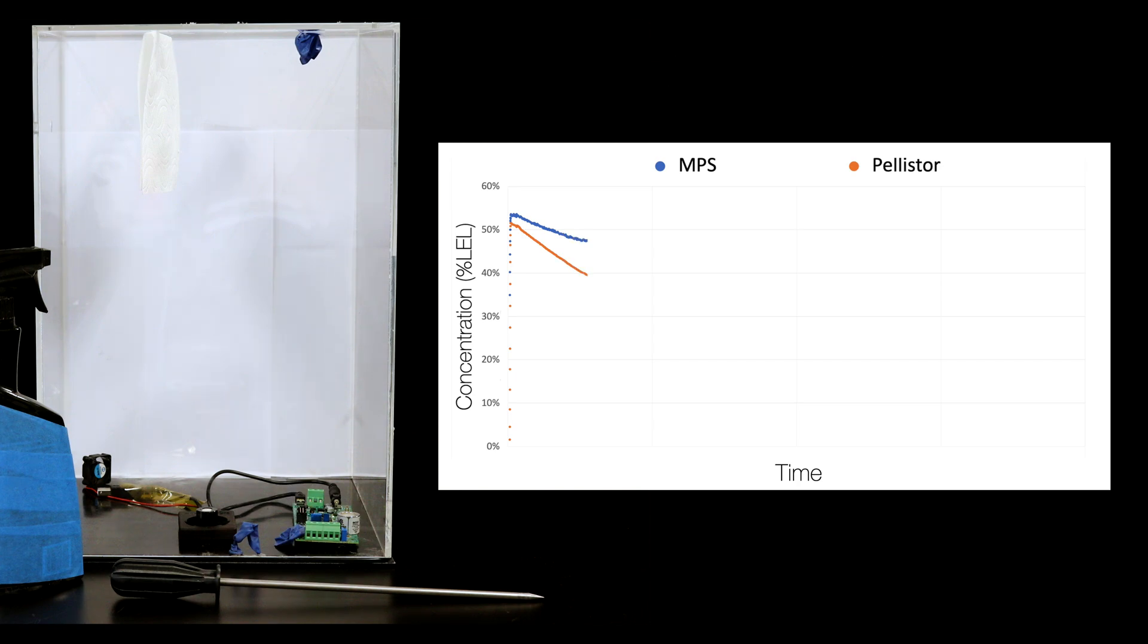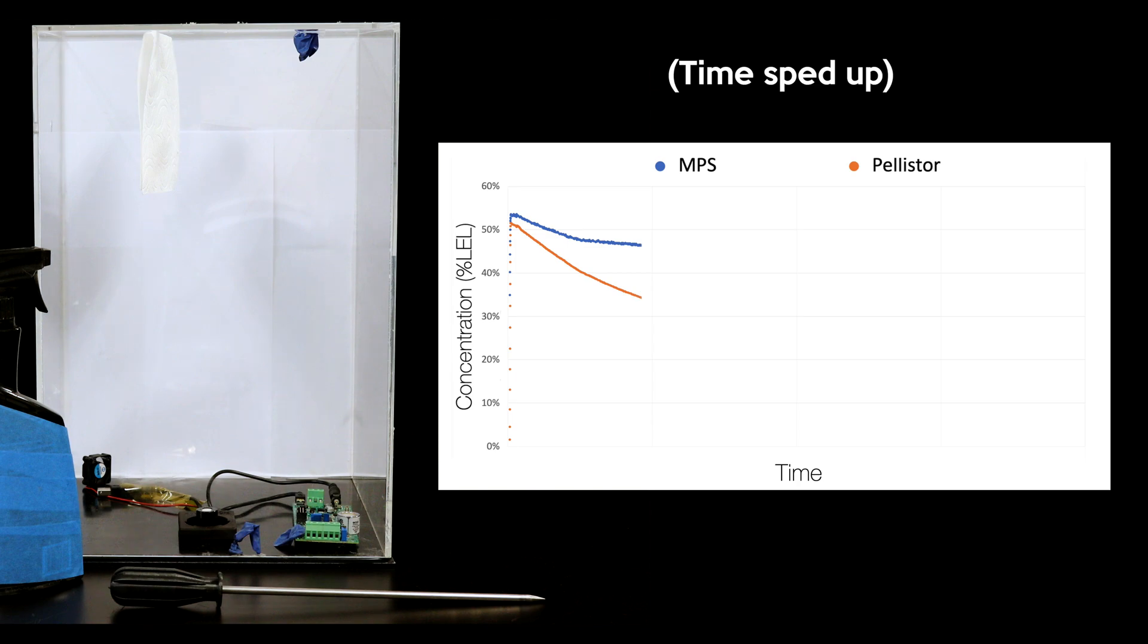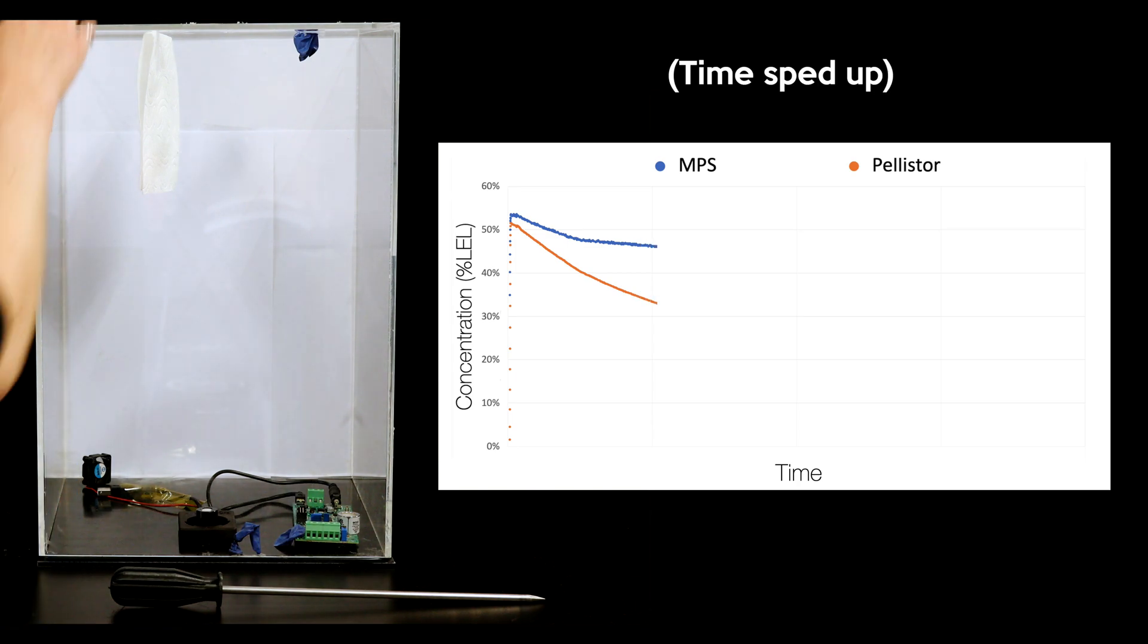Now that the methane is evenly distributed in the chamber, I will spray in a silicone-containing substance and measure the response of each sensor. The methane concentration in the tank will allow us to see any response degradation from the poison.